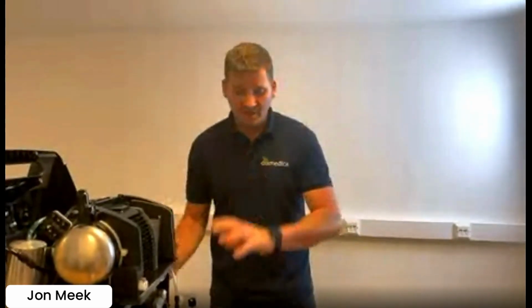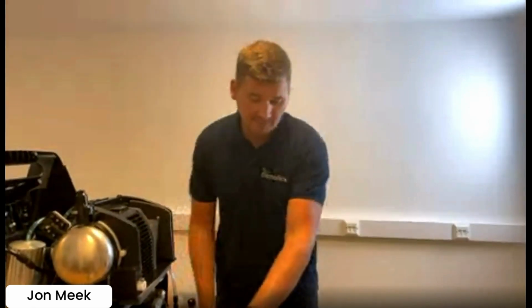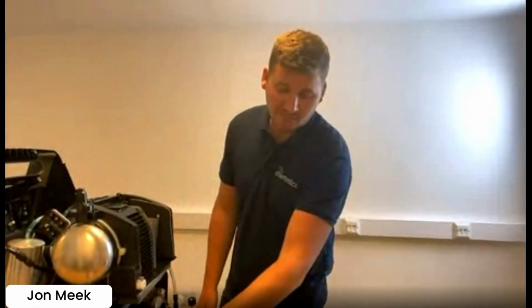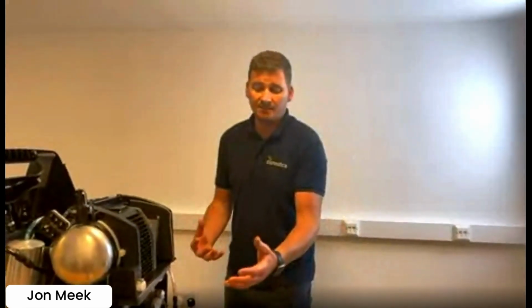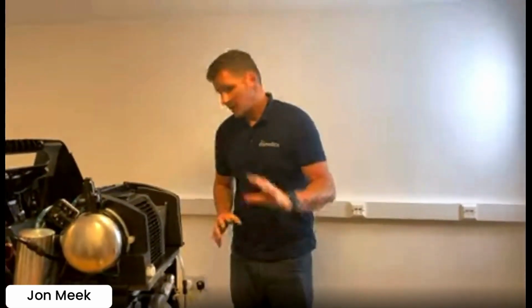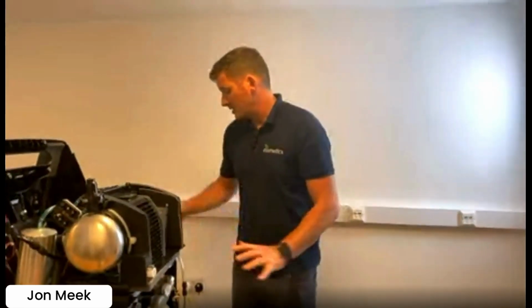Most of the machines have temperature controlled ones. We use the heat generated from the compressor. It gets really hot, so we're using all the warmth from the compressor, generated at a steady flow rate, to warm the humidifier bottle itself. I hope that answers the humidification question. For the CPAP one, I think you said 16 litres a minute. On the old one, yes, it goes up to 16 litres a minute on the AirSet.